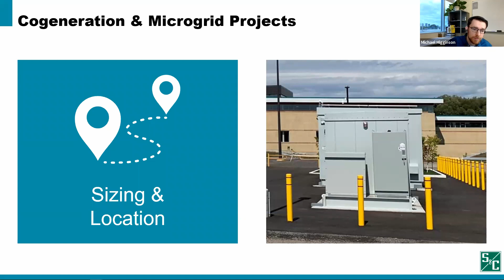Now let's overview the interconnection process. As we just covered, the first tasks are to identify the size of the resources we're going to interconnect and where they're going to be located. Once there's a concept of the size and location, a prudent next step is to start discussions with the utility. This discussion can cover points of interconnection and circuits we could be interconnecting with. Often DoD facilities have multiple circuits serving them to ensure reliable power supply to their critical loads, and interconnecting to a specific one of these circuits might have advantages. Based on the discussions with the utility, the design can iterate to develop the most effective design and connect to the best circuit and location for the project to succeed.